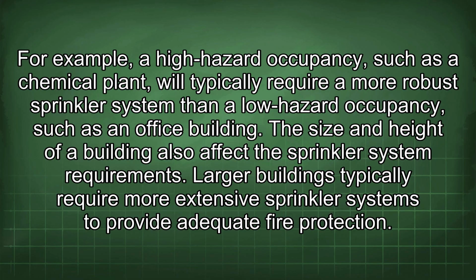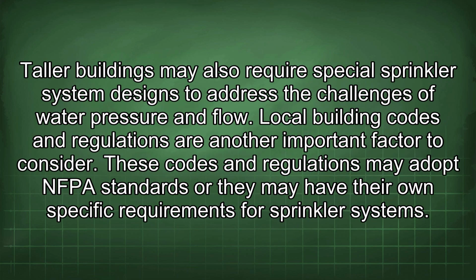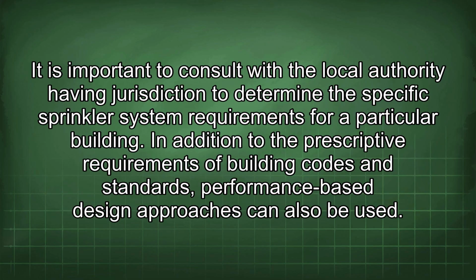The size and height of a building also affect the sprinkler system requirements. Larger buildings typically require more extensive sprinkler systems to provide adequate fire protection. Taller buildings may also require special sprinkler system designs to address the challenges of water pressure and flow. Local building codes and regulations are another important factor to consider. These codes and regulations may adopt NFPA standards, or they may have their own specific requirements for sprinkler systems. It is important to consult with a local authority having jurisdiction to determine the specific sprinkler system requirements for a particular building.